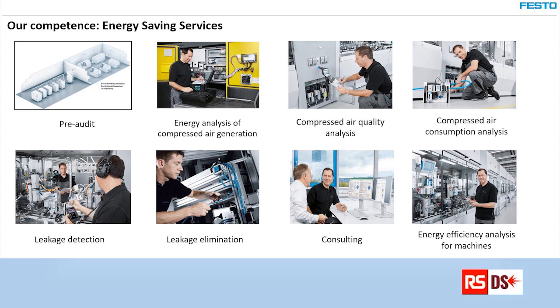And then we can calculate how big the leakage level in the complete plant is, because we know how many leakages we can find during an hour or during a day. And then we can calculate this. And with all this data, then we are making a report.